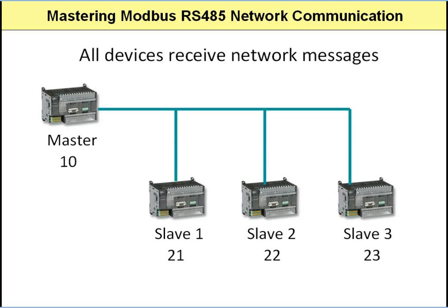What they do is that they pull the message apart when they receive it, every single one of them. They get the Modbus Unit ID of the message and then compare it with their own stored Modbus Unit IDs. It is only if the received ID matches their internal Modbus ID will they respond. So in our example, since it is only equal in the case of slave 2, it is the only slave that responds. Slave 1 and slave 3 simply don't do anything at all. So slave 2 will respond with a message back to the master.